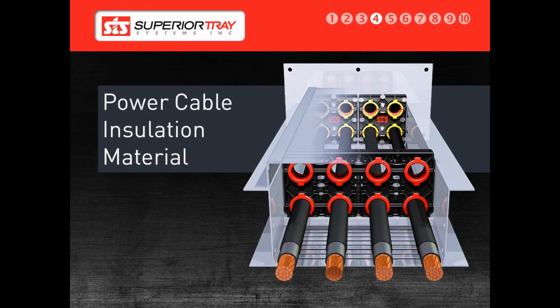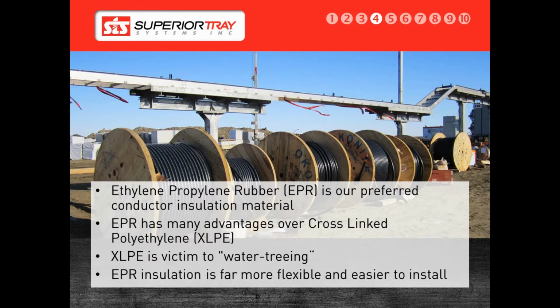The fire rating on power cables is generally based on insulation materials. The preferred insulation material for a cable bus cable is ethylene propylene rubber, or EPR, with an outer jacket made from PVC or chlorinated polyethylene, also known as CPE. The outer jacket is typically what determines the fire rating. EPR has many advantages over XLPE.